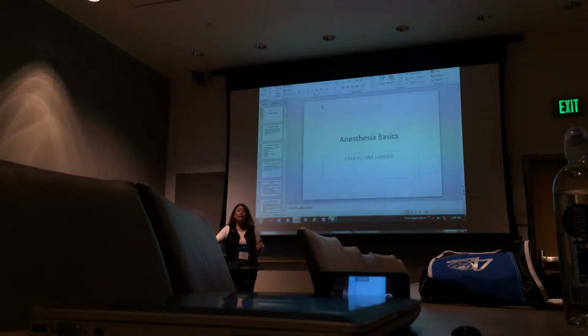And that's something that we cannot tell the clinician to do. We can't tell them how to practice. All we can do, if we get a complaint on a machine like that, is put it through its paces and make sure that it's functioning according to manufacturer specifications. But don't dare tell them how to practice. And you could say, there could have been a leak anywhere in the disposables. That covers everything.